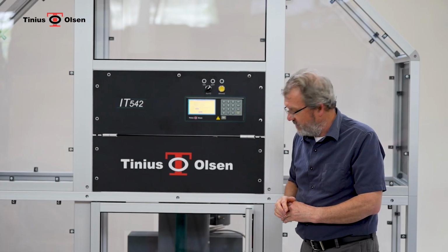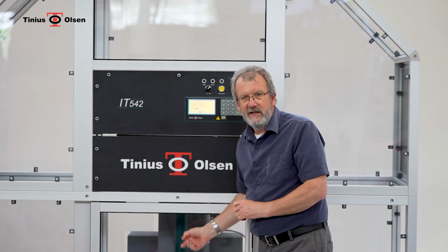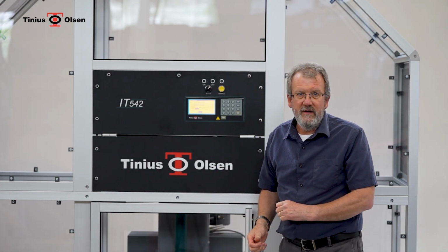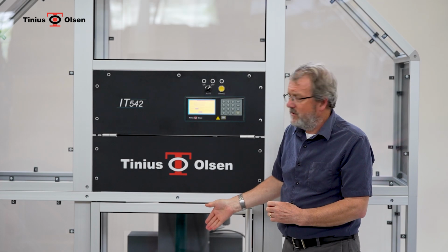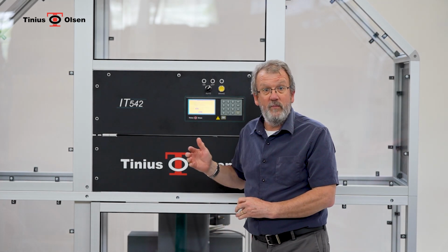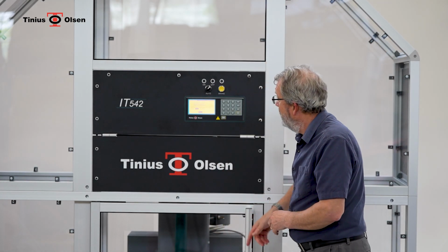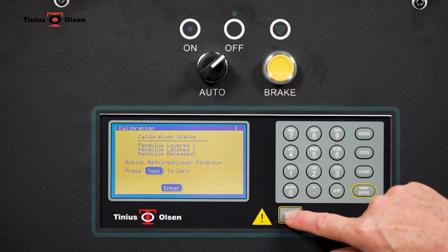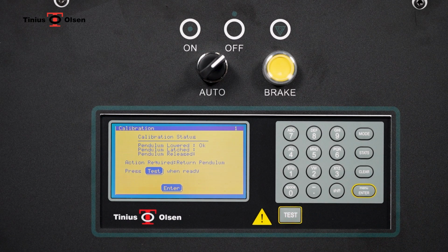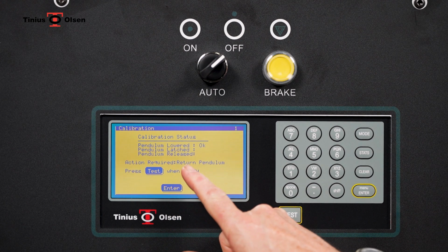It is very important that the pendulum is hanging completely stationary at this point. This is where the machine captures the 0 position for the pendulum, where it is to strike a specimen. It says press test to 0. Pressing that test button records that location. It then says action required, return pendulum.